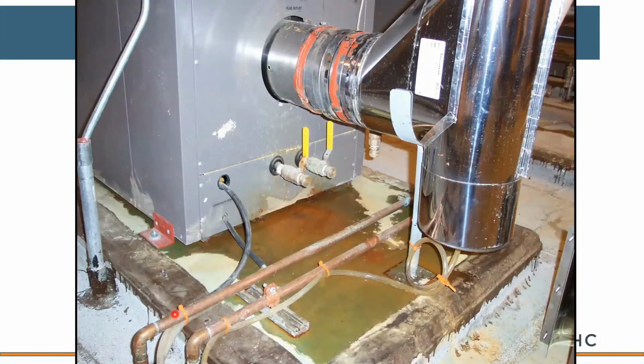A good example of a boiler that's installed with a vent issue. This is an 87, 88% efficient boiler, not designed to condense in the boiler, but it takes enough moisture out of the products of combustion that it has potential to condense in the stack, or the flue. The contractor originally installed this with galvanized vent or B-vent and ran a long radius elbow straight up through the roof. It took about 3 months for the acid occurring in the condensing process to eat holes in the venting.